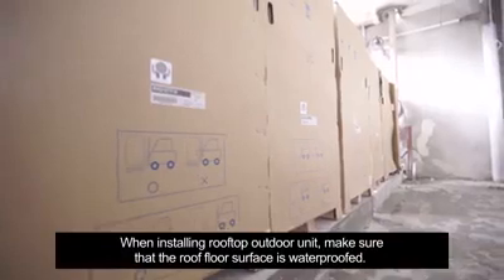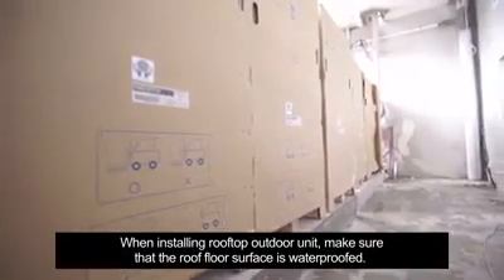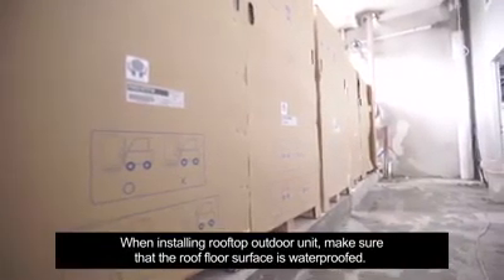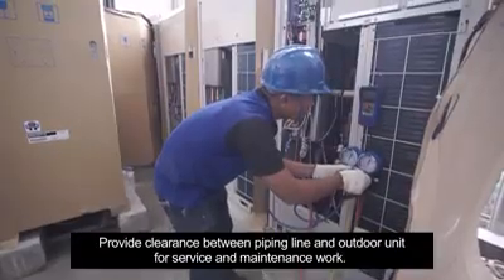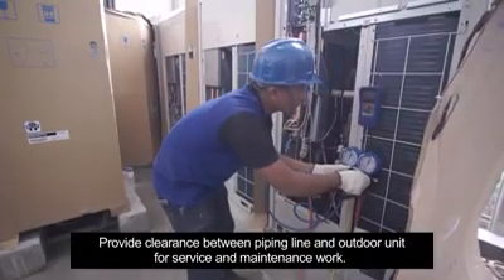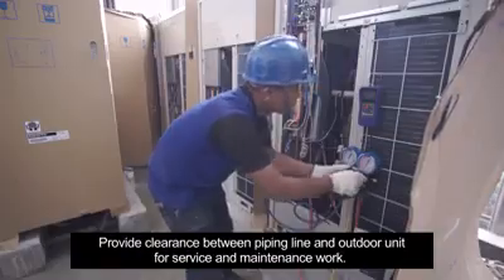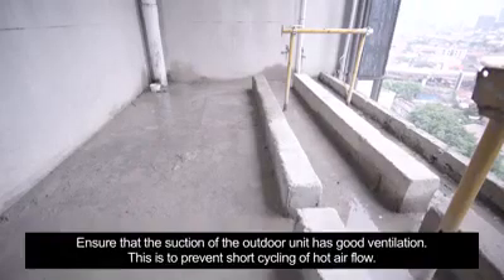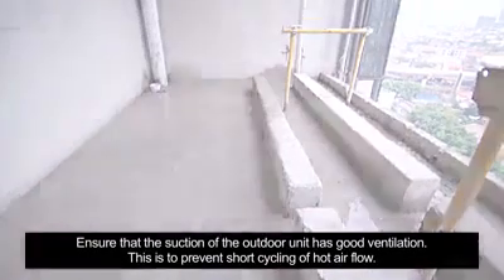When installing rooftop outdoor unit, make sure that the roof floor surface is waterproofed. Provide clearance between piping line and outdoor unit for service and maintenance work. Ensure that the suction of the outdoor unit has good ventilation. This is to prevent short cycling of hot airflow.